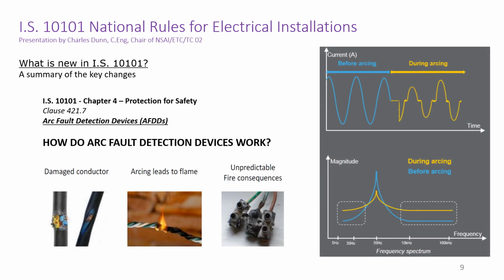Like all new switchgear, it will take time for the market to get to grips with how AFDDs work. The idea is to monitor the circuit to detect an arc fault before it can cause a fire. The AFDD does this by monitoring the electrical power wave, looking to see the normal sine wave curves. Deviation from the sine wave indicates something is wrong in the circuit. The electronics in the AFDD, like the electronics in an RCD, can determine if the deviation from the sine wave is caused by an arc fault. Then the AFDD disconnects the circuit.